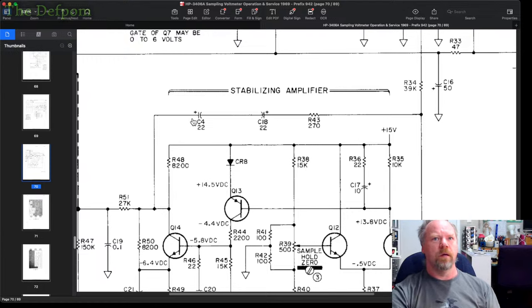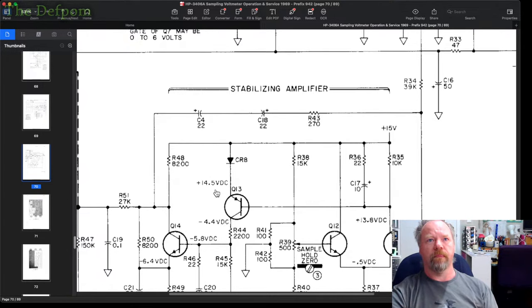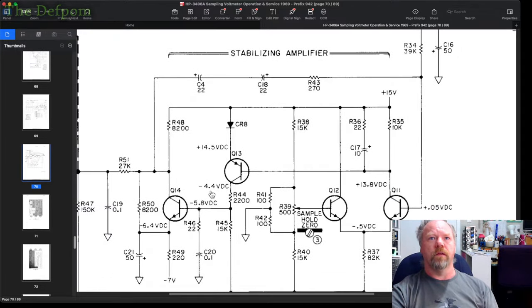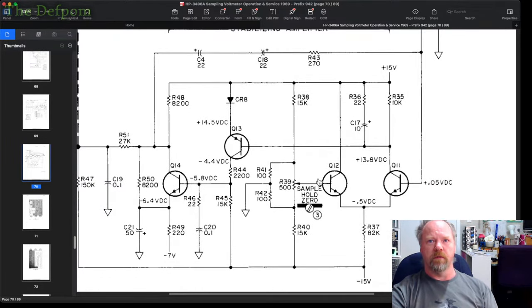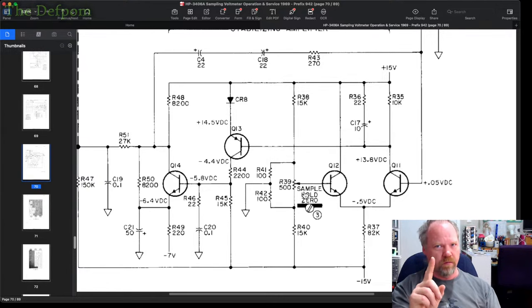And it's got these back-to-back capacitors here, which means this is AC sampling through here. That's what back-to-back means. So this is the amplifier section, and it's got these mirrors here, so it'll sample-hold 0. I've tried changing that, with minimal effect. It does affect it very slightly, but I'm on that 0.03 volt range, and have a meter reading I can see instead of being off scale, then I'm getting that sample-hold 0. I can adjust it very slightly, it moves the needle just a little bit, but it's almost insignificant.